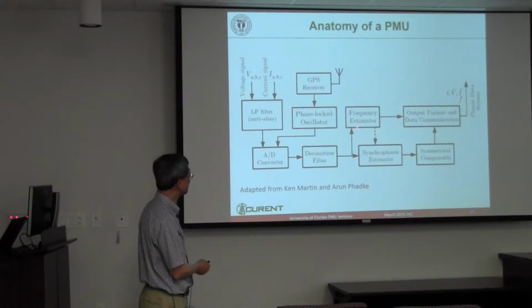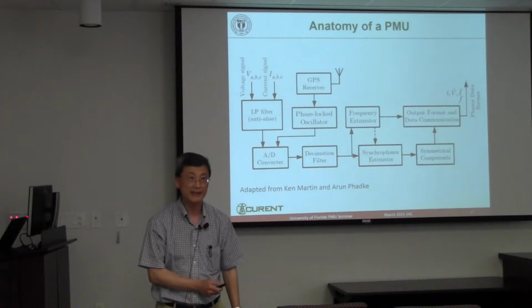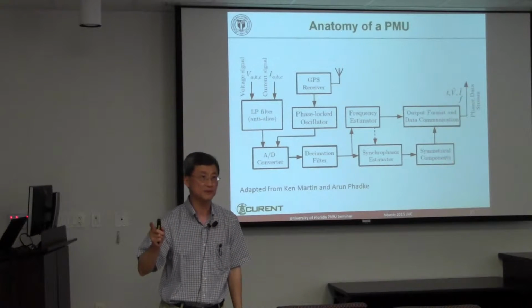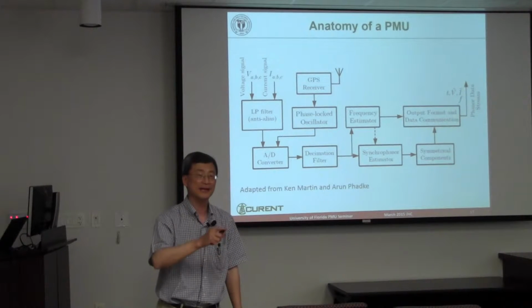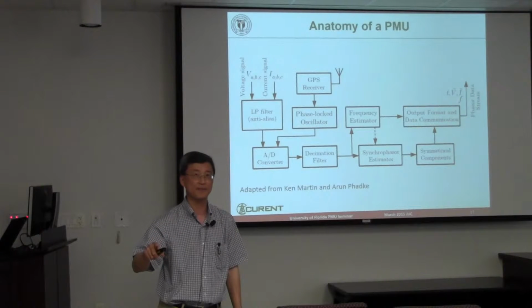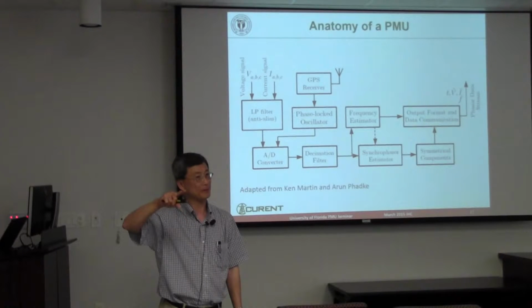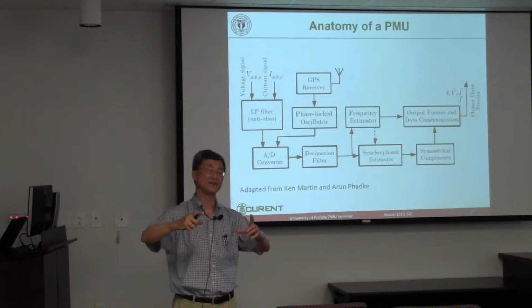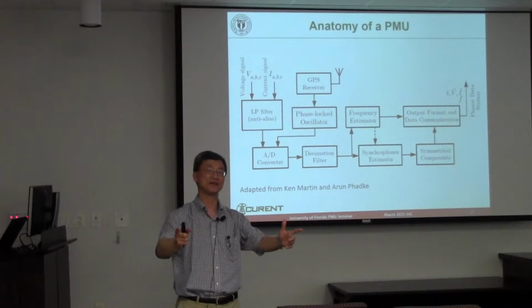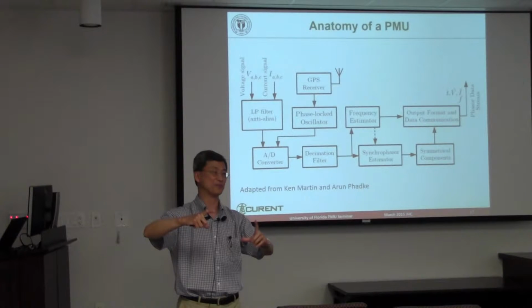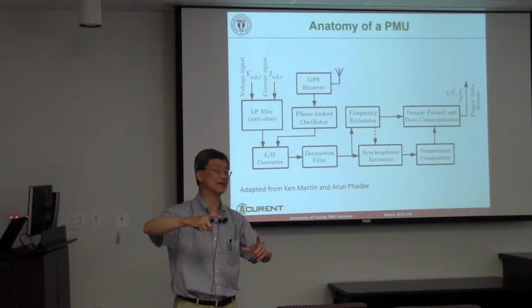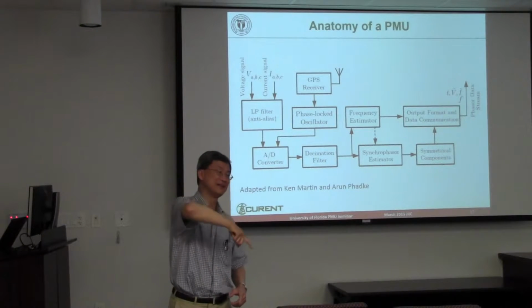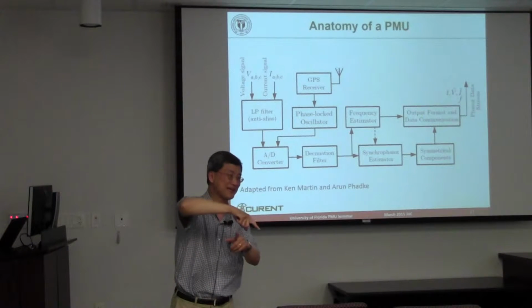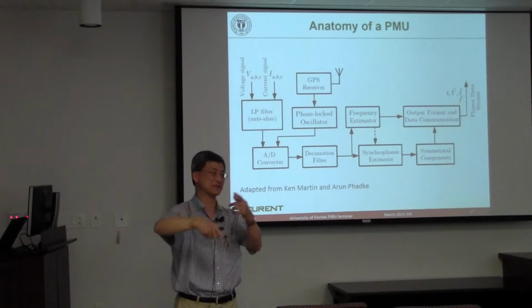Another issue is that you actually have to estimate the frequency. The power system rarely runs at exactly 60.000000 hertz — it's more like 59.997. So anytime you have a slightly off-nominal frequency, phasor calculation imposes a second harmonic on the magnitude. At 60 hertz, a complete cycle calculation traces out a circle, but with an off-nominal frequency, the phasor traces out an ellipse instead. As the ellipse goes around, its amplitude changes — that's the second harmonic. Every cycle, you see one of these going through.